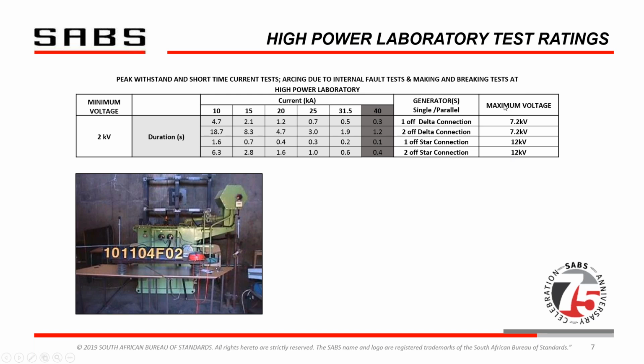They're always connected in parallel, because of course if you connected them in series, the stator voltage would need to be 28 kV, not 14 kV. And here are the fault currents that can be achieved from 10 to 40 with the different connections.